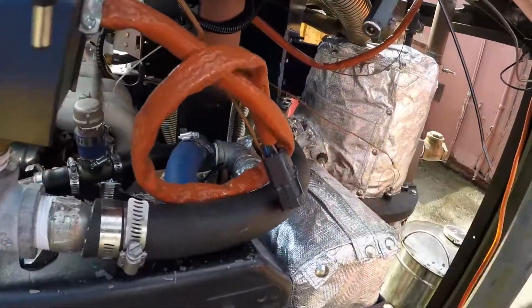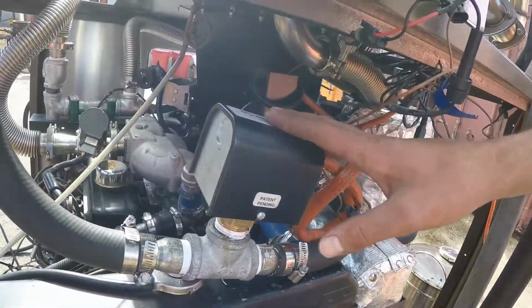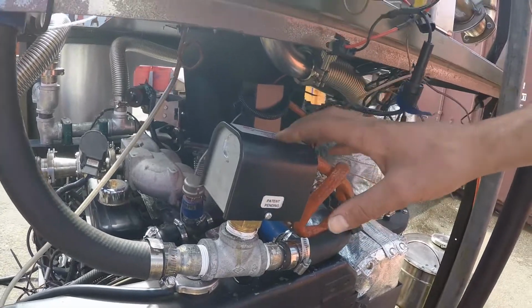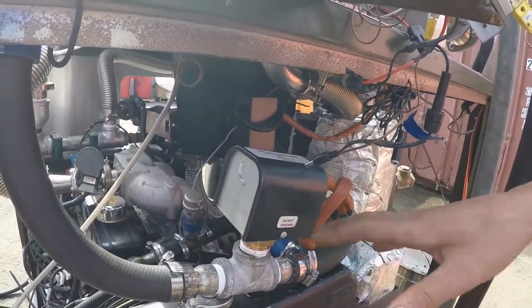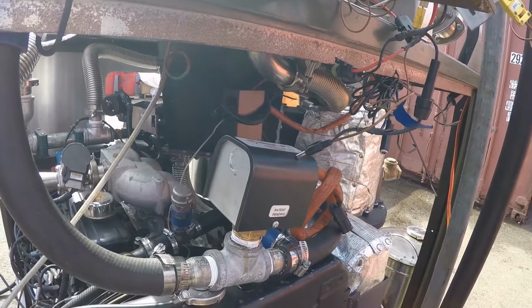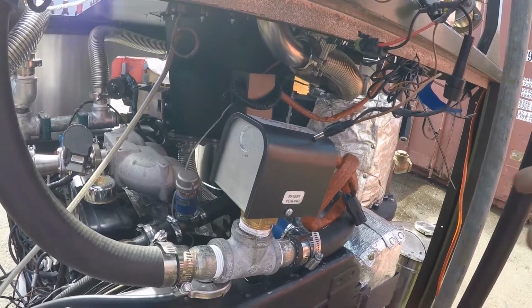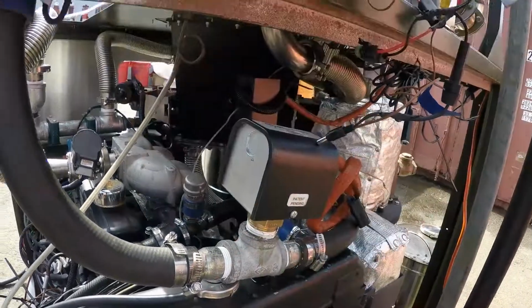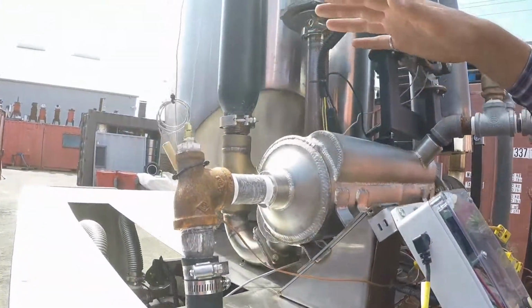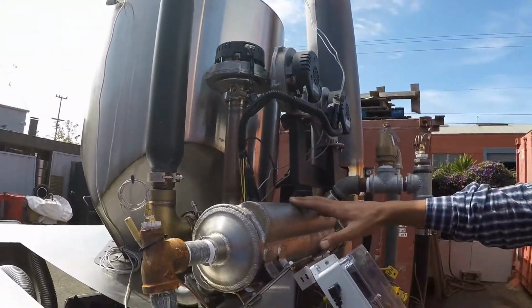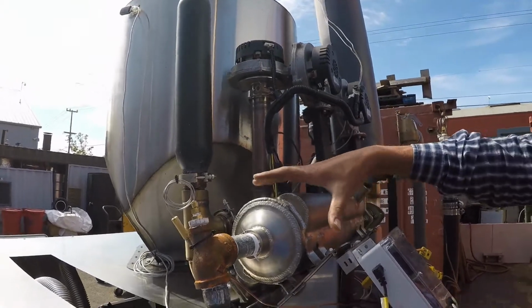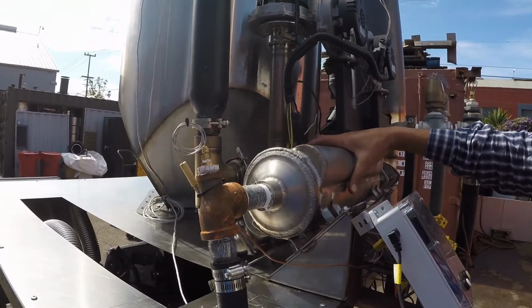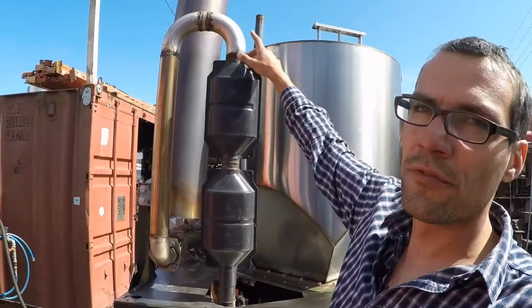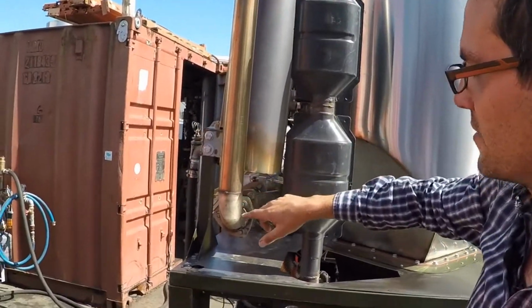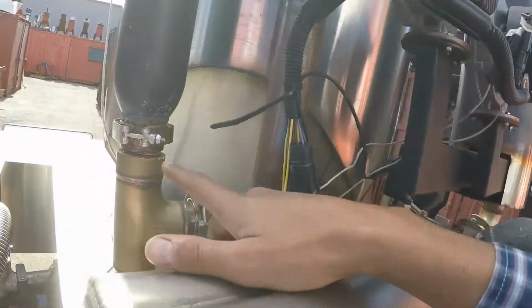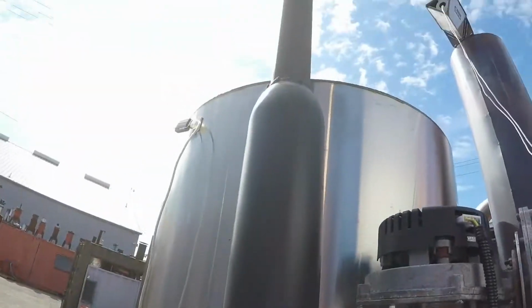Comes out of the heat exchanger, and then we've got it going through a flow switch. This is where we detect flow in the system to make sure that the combined heat and power working loop of fluid is running. From there, we go up into a shell and tube heat exchanger. In this heat exchanger, the water is on the outside, and through the middle, the exhaust gas passes, and then exhaust gas comes out the heat exchanger and out of the exhaust stack.